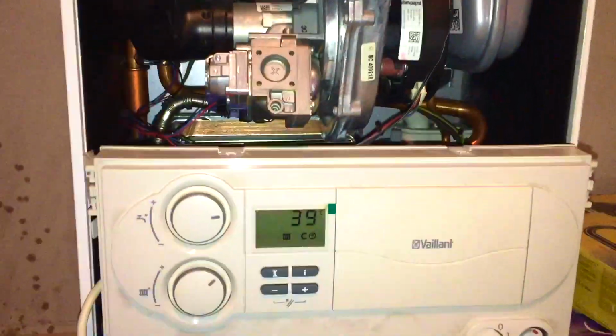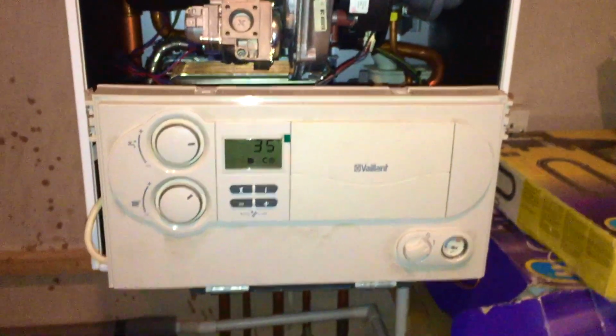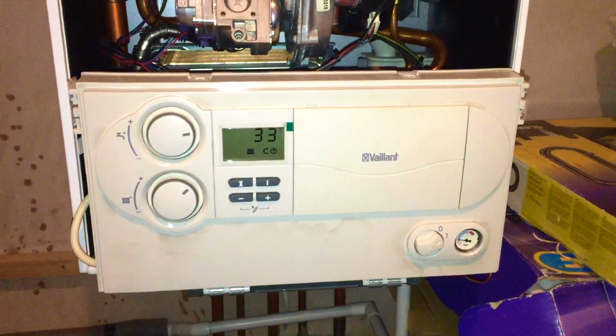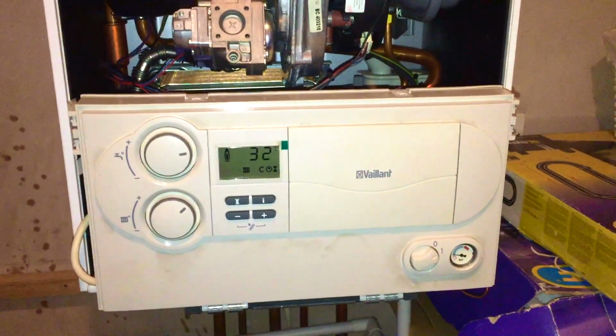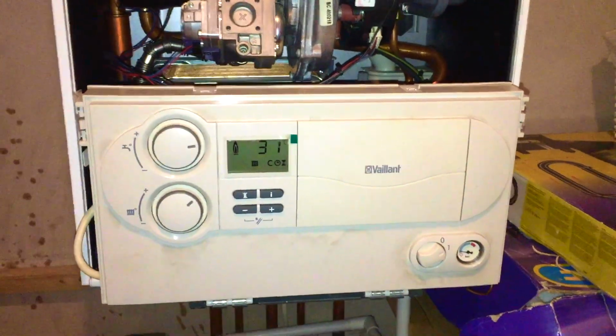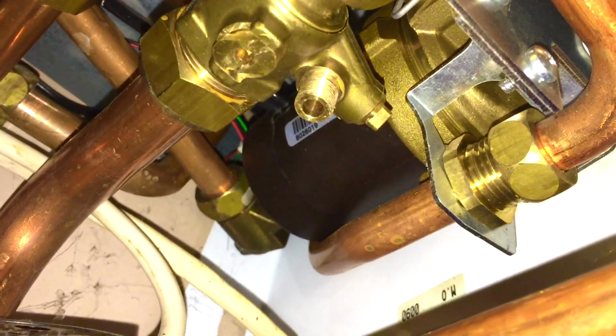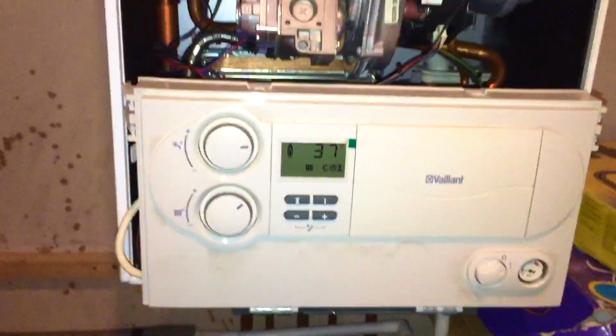Okay, while I'm here with this 937, I'll also give you some little tips on F81 F91. In my experience, F81 F91 is usually the pump up the back here has failed. It's that black and brass pump up there. Usually it's that.